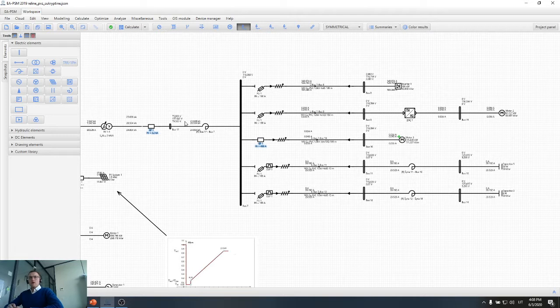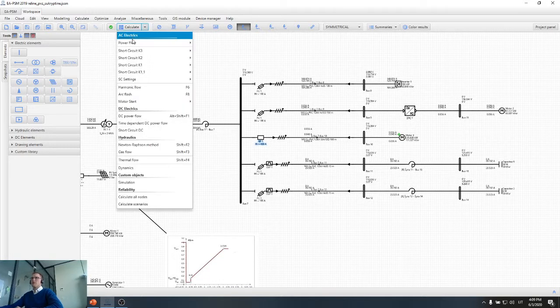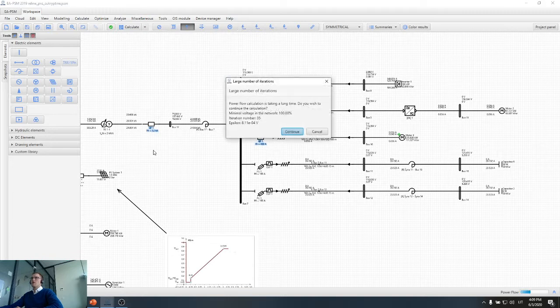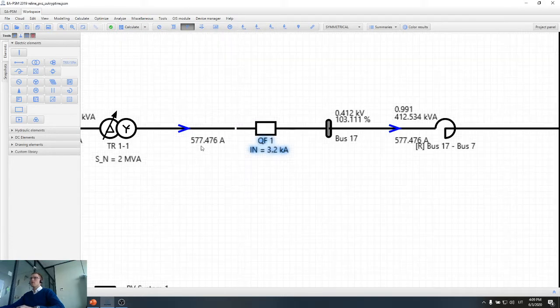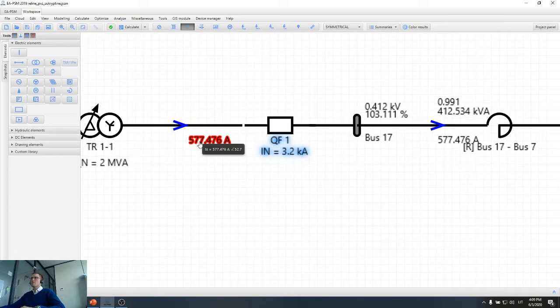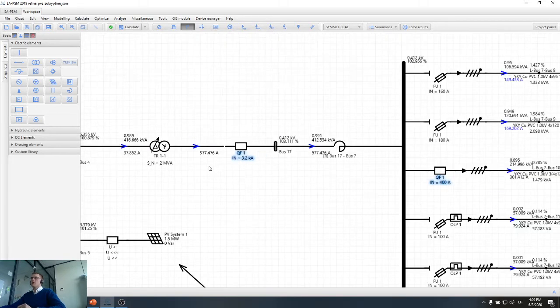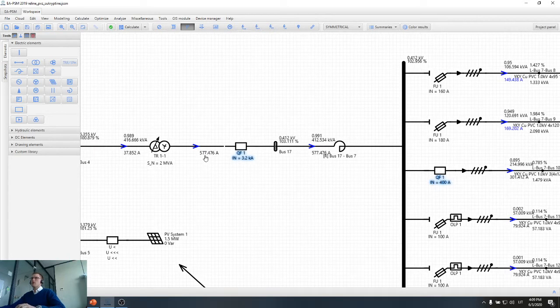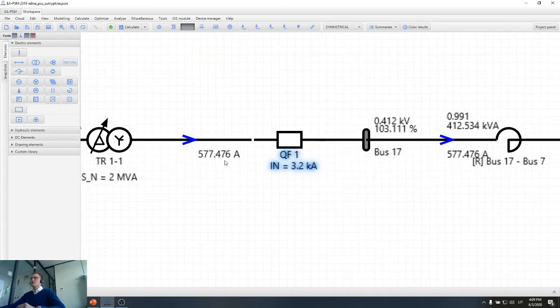One more question. What are the parameters that should be considered while selecting the main equipment like a circuit breaker? So the main parameter, as I have mentioned, is first of all the power flow current. Let's say 577 amps. The circuit breaker should have a bigger nominal value than the calculated load flow current. Here we can see that the calculated current is quite a bit smaller than the nominal value of the breaker.